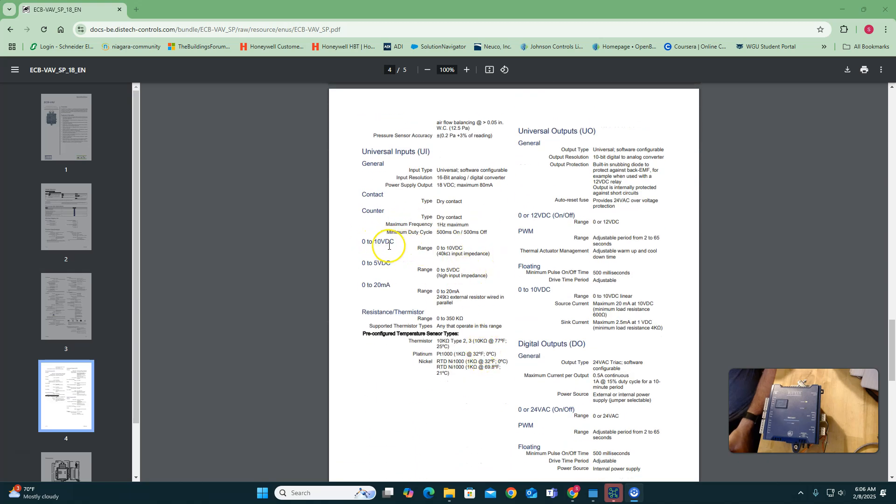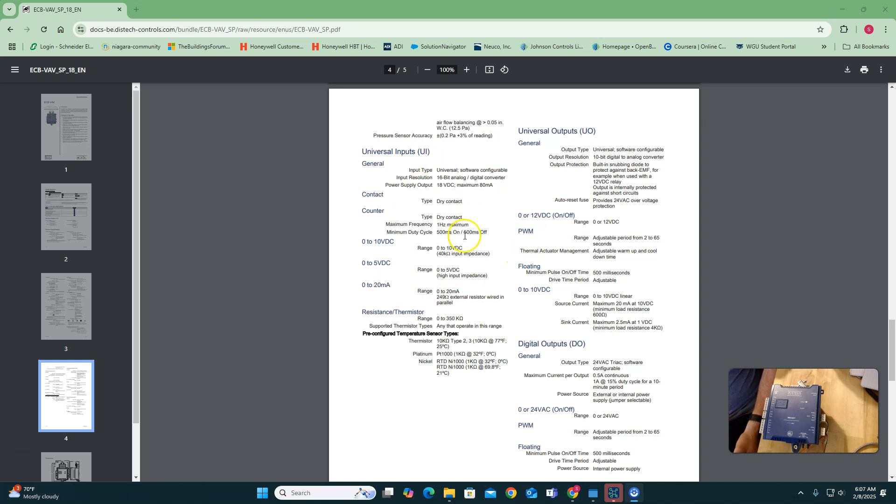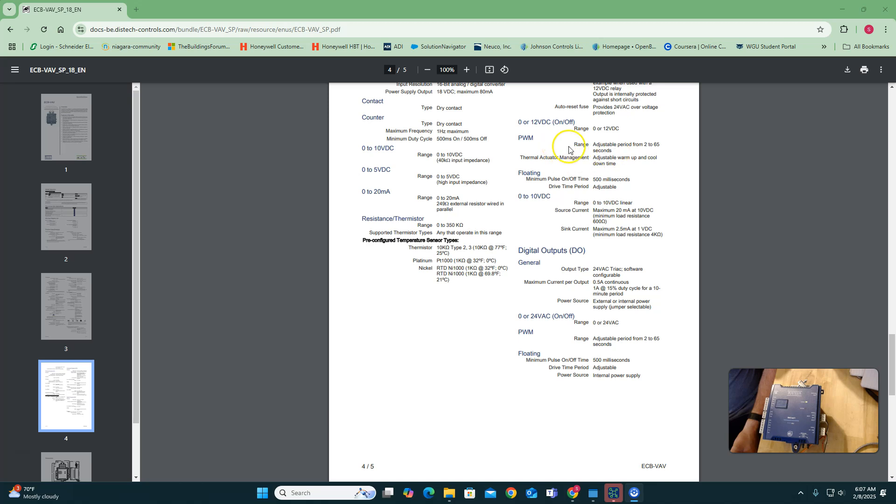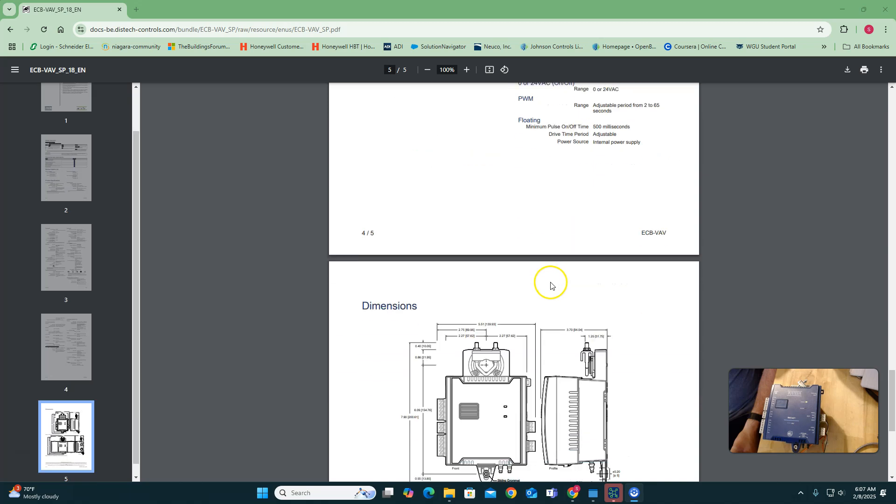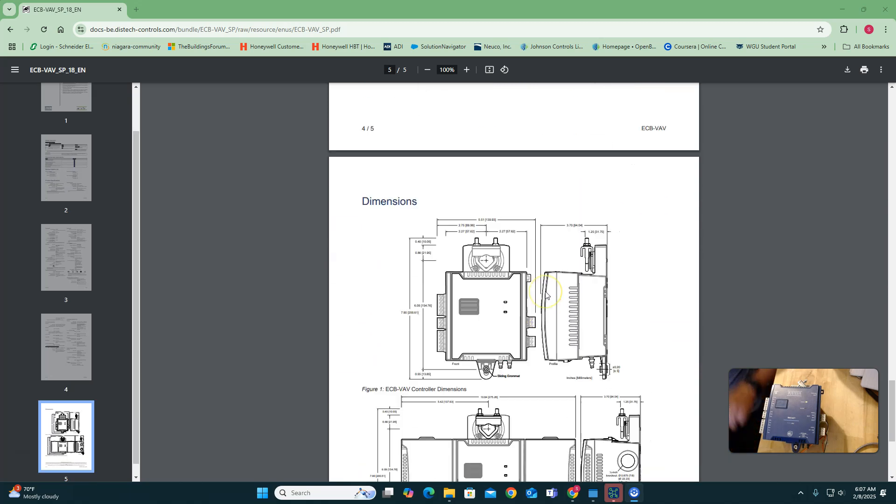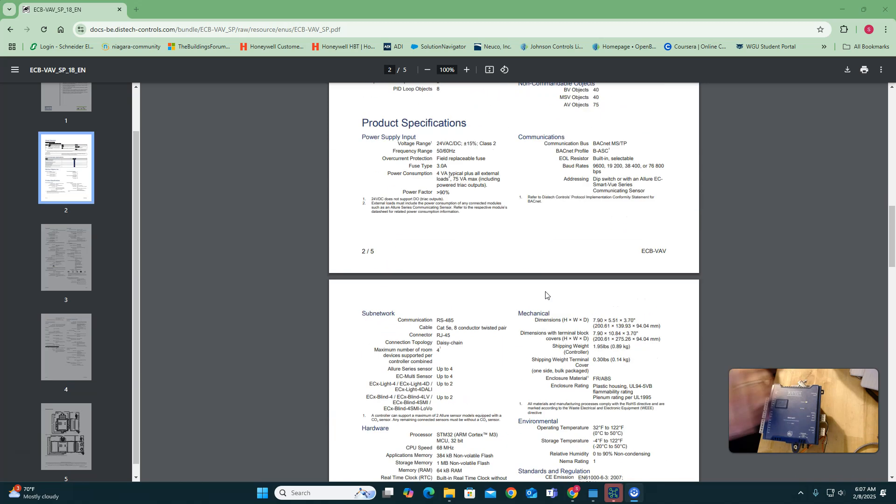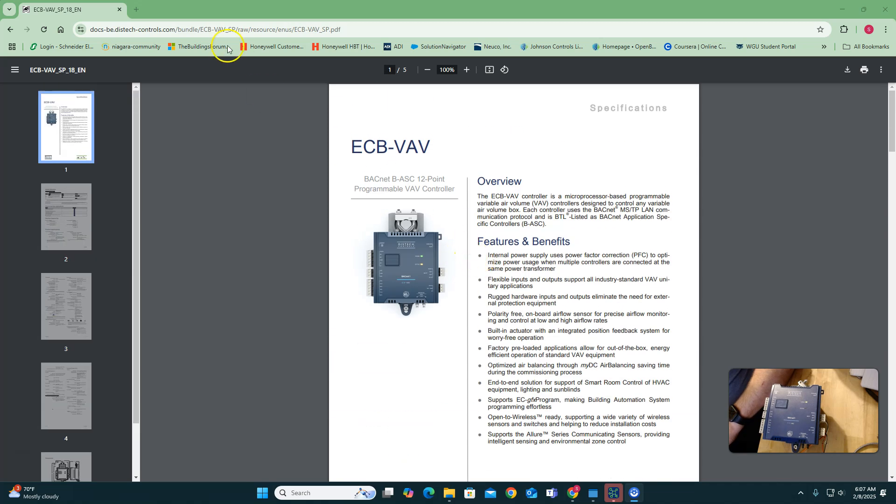It could do your standard zero to 10, zero to five, zero to 20, four to 20 milliamp basically, but you do have to put a resistor in line and parallel with it on the four to 20 signal on the input side. Just, just so you know, it does not, you can't hook it up directly four to 20. You do have to put that resistor in there. We learned that the other day. Pulse width modulation. That's pretty cool. And floating and that's it. Now, the DOs will actually output 24 volts hot on the VAVs. Whenever you get into the unitary controllers, that's where you got the 12 volts DC. So you need to put a relay in there, 12 volts DC, if you're looking for 24 volts.